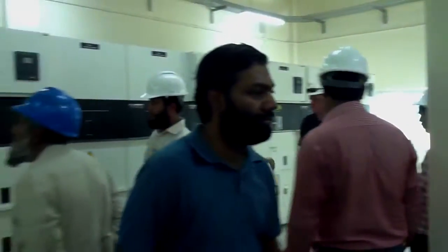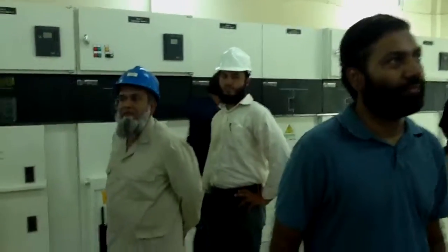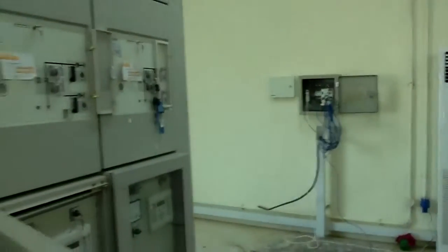Gas insulated switchgear that is introduced in this wind turbine industry for the first time in Pakistan. All the turbines are producing voltage at 690 volts, right? And from 690 volts, the voltage is stepped up to 22 kV from the GSU transformers. And from those, we have 4 groups in our wind farm: Group A, Group B, Group C, Group D.